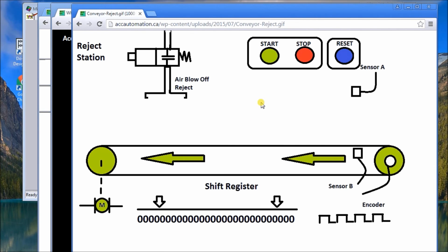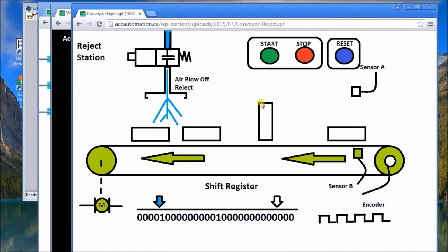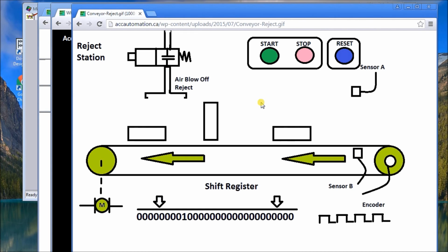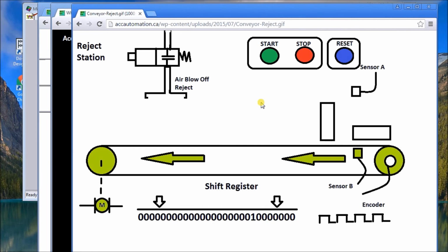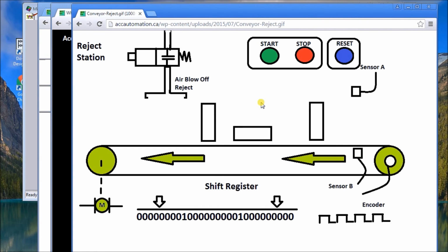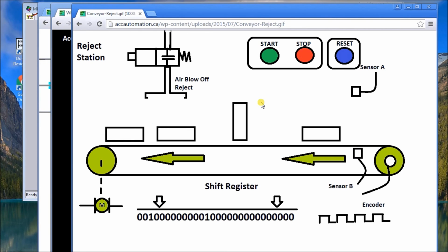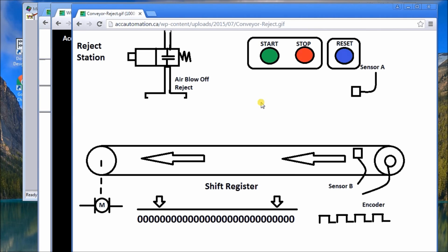So using these three methods, in the PLC we have normal discrete bits, which can be memory retentive or non-memory retentive. We use numbering systems, and the more common ones are always binary, then hex, BCD, and sometimes there's octal in there. And lastly, position. Positioning is tracking these bits. So viewing bits these three different ways will help us in programming the PLC.